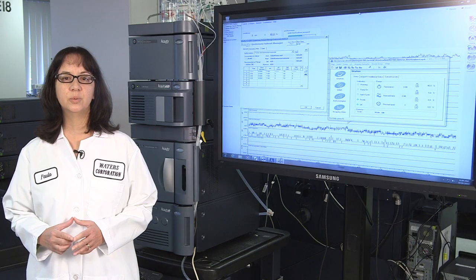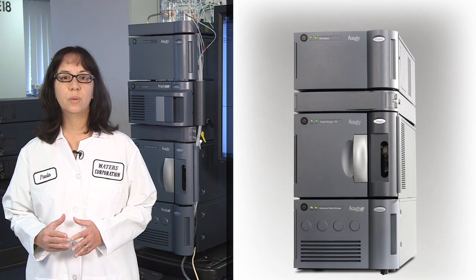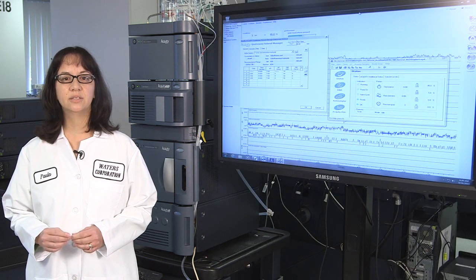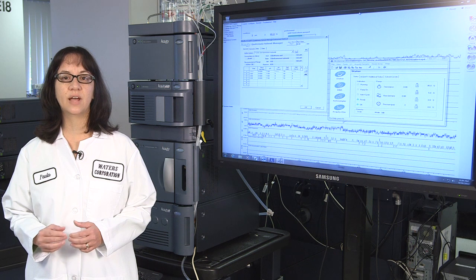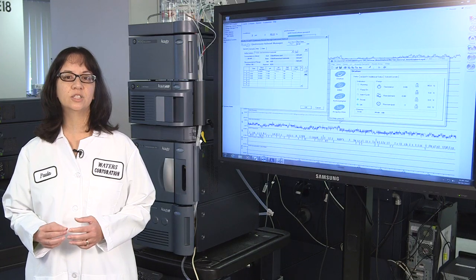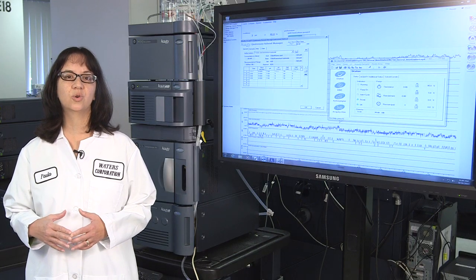At Waters, we have been working on ways to use our Quaternary Acquity UPLC H-Class system as a tool to automatically blend buffers to control mobile phase pH. Our technique is based on the established principle of acid-base equilibria, where a buffer of desired pH can be created by mixing solutions of a weak acid and its corresponding salt or base.